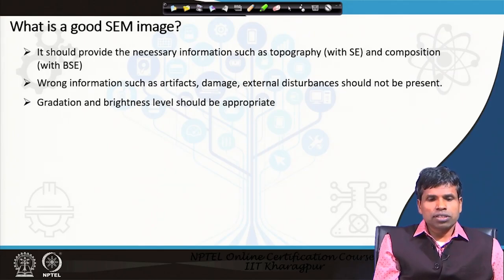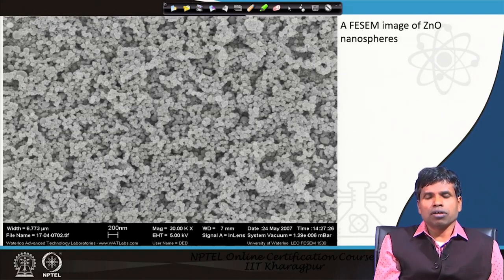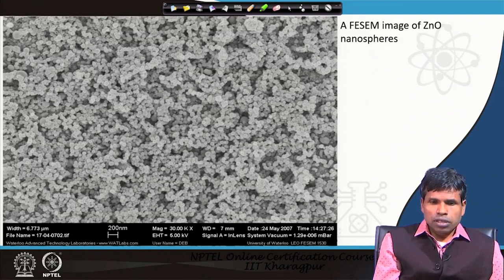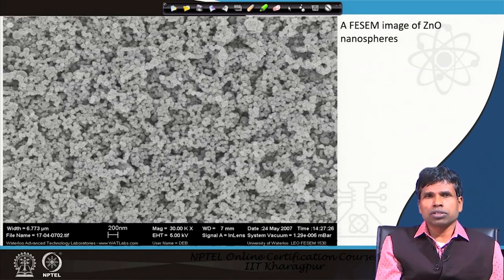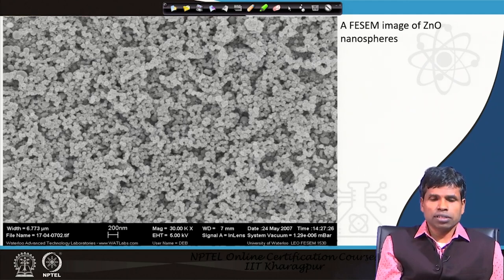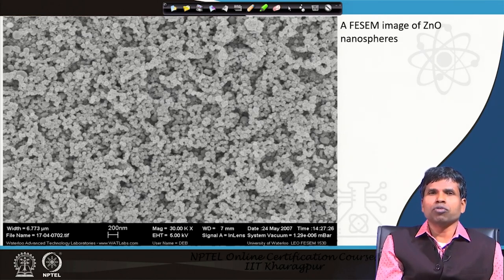Now, let us see what a good SEM image looks like. Here you see a field emission SEM image of zinc oxide nanospheres. The brightness and contrast are quite uniform throughout the region — it is not more bright on one side, every area is equally and well focused. The brightness is not too high, contrast is not too high; it is in an optimum range, giving uniformity across the image area. You see small spherical particles that are three-dimensional — that is why we can say they are spheres.